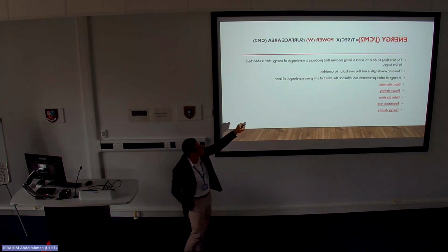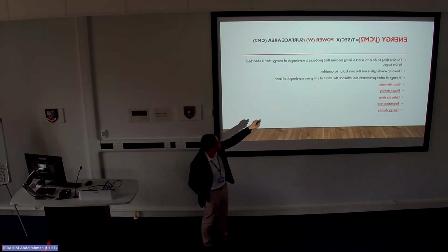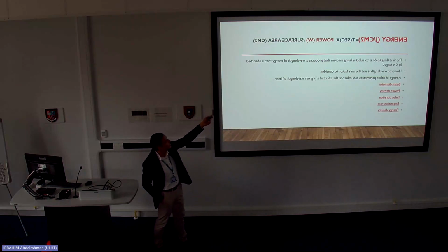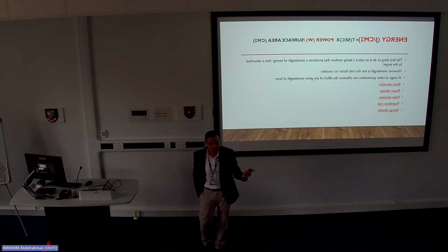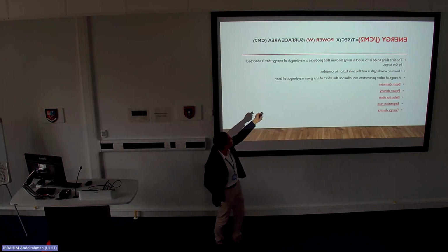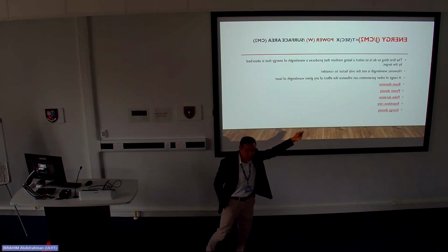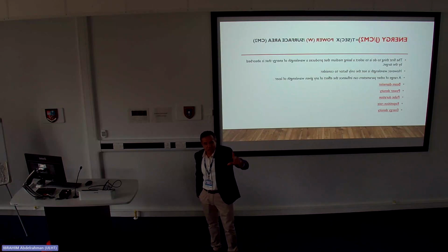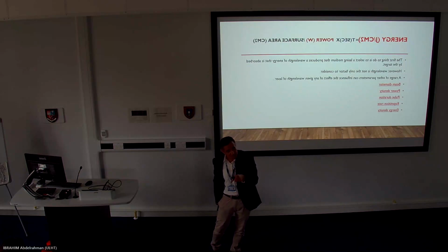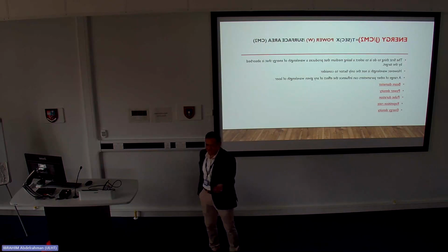So what else? The power. The power is also directly proportional to the energy, so the more you put in, the more effect you get. The last bit is called the surface area, which is the beam that I've mentioned before. The beam is inversely proportional to the energy. So if you use a dot, you're going to deliver much more energy. If you do it as a linear or semi-lunar shape, which is larger in diameter, your energy will be lower, because it's an inverse proportion.